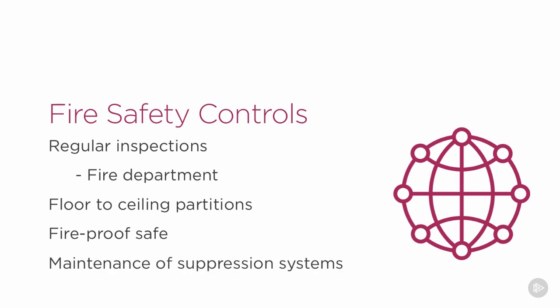Make sure that the systems we have are maintained. We talked about handheld extinguishers, making sure they're being reviewed, but also we had a very serious fire in a server room a few years ago where they'd come to do maintenance, and when they do maintenance on the flooding system, they put in a safety key so it does not trigger the fire suppression system by mistake. But this company that had done the maintenance forgot to remove the safety key. And so when they had a fire shortly after, well, the fire suppression system never triggered on because the safety key was still in place. But regular maintenance and review of these systems, of course, is important.